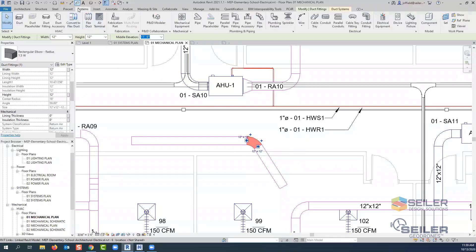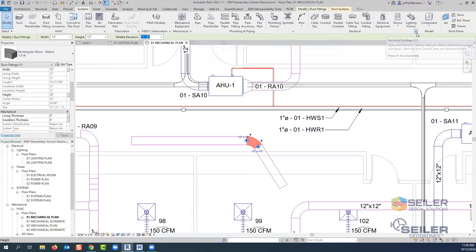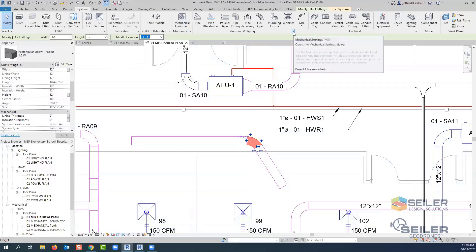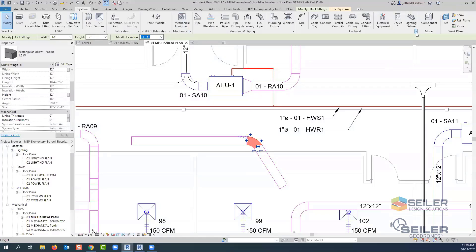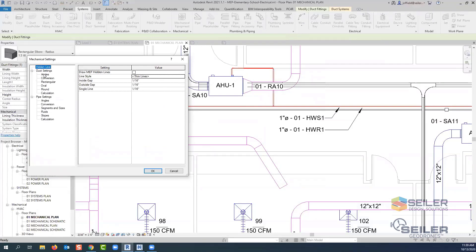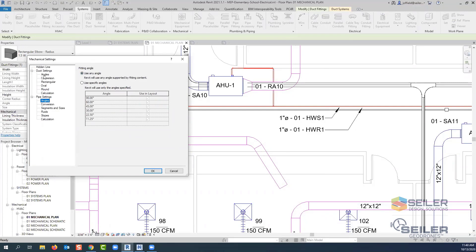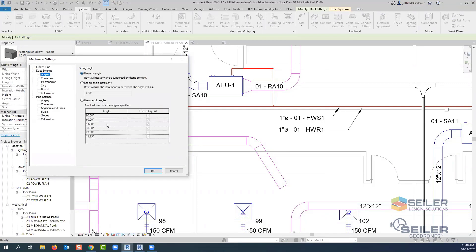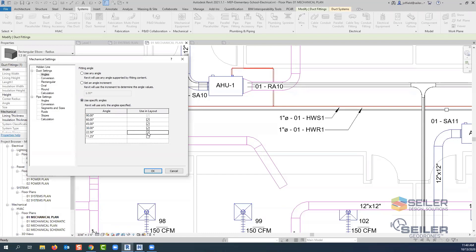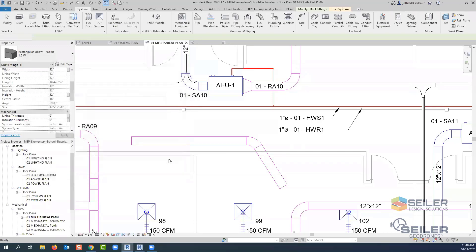If you go into your systems tab within Revit and right below HVAC, your mechanical equipment, piping and plumbing and electrical, you're going to see these little drop down arrows. And these go into either the mechanical settings, which include piping and or your electrical settings. If we'll go into our mechanical settings first, let's look at our duct and our pipe angles. Notice how it says use any given angle right off the bat. That's how Revit is default out of the box. So if you want to set an angle increment, you can do that. And you can do that by whatever degree you want or use this last option here for specific angles. So now if we want to force everything to be 45 or 90, we've only got those two options on there.